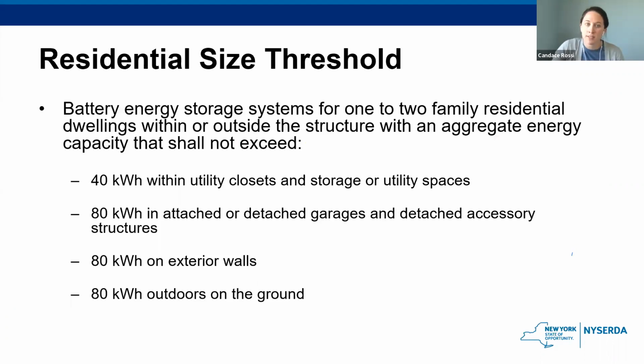So here we have the residential size threshold. The residential threshold sizes shown here are from the 2020 Residential Code and are subject to all the requirements here. Each individual unit may not exceed 20 kilowatt hours, and systems that exceed these sizes will have to follow the requirements in Section 1206 of the Fire Code of New York as applicable.